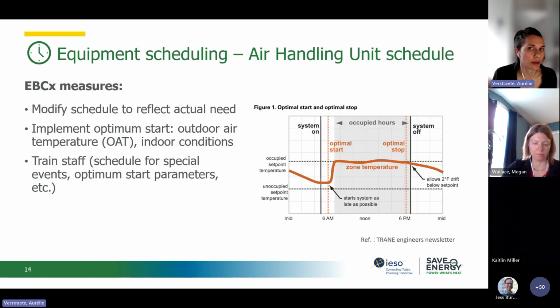So in that case, what could be the measure to implement here? Of course, modify the schedule to reflect actual need. You can implement a special sequence, which is called optimum start. So here you want to start the system as late as possible. The system will automatically start several hours prior to occupancy during the coldest days of winter, but very close to occupancy time during mid-season. That sequence will consider outdoor air temperature and indoor conditions. Finally, you want to train staff. You want to train operation staff on BAS scheduling capacities to answer future needs, for example, for a special event during the weekend. You also want to train staff to know about optimum start parameters.